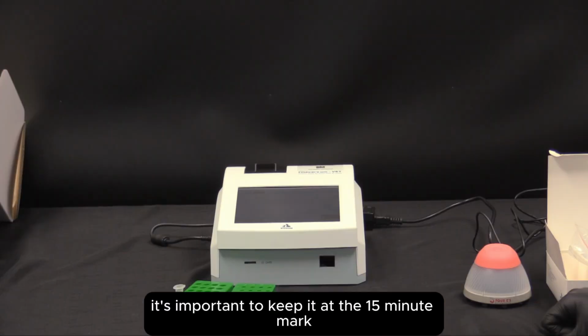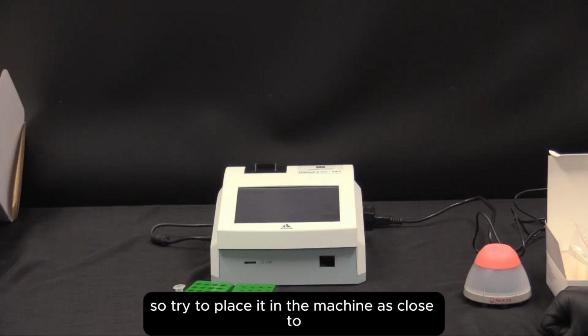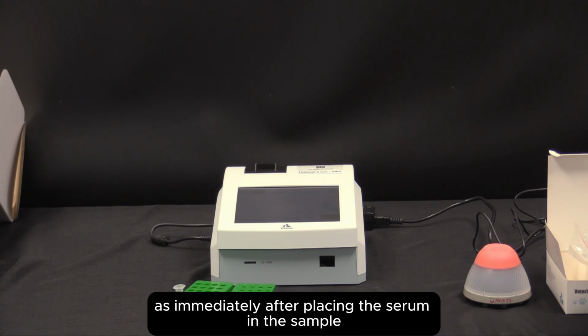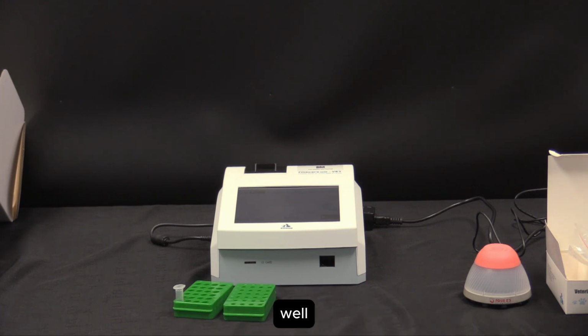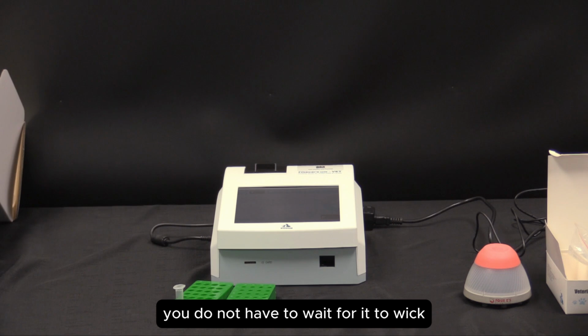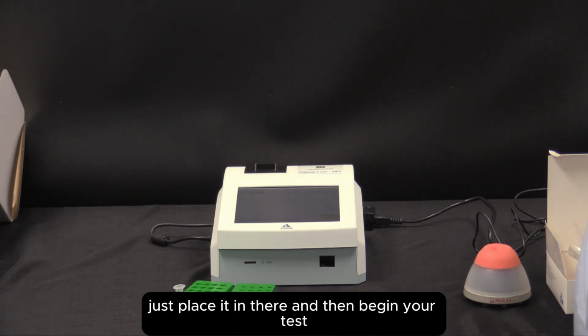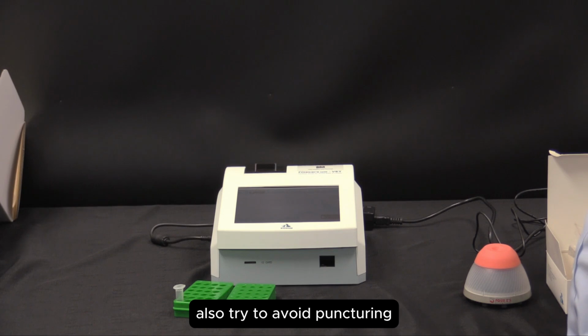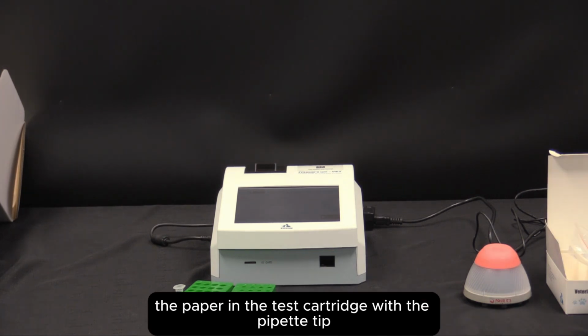It's important to keep it at the 15-minute mark, so try to place it in the machine as close to immediately after placing the serum in the sample well. You do not have to wait for it to wick all the way through. Just place it in there and then begin your test. Also, try to avoid puncturing the paper in the test cartridge with the pipette tip.